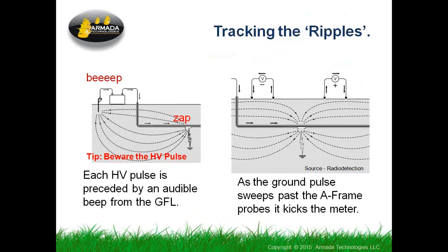I should mention that because that's a 2400 volt pulse, at least, coming out of the unit, you want to be careful with handling this. Once you've got it set up, you connect it like a locator, and a locator puts out a high voltage too, but not this high. You connect it like a locator and start doing your work out in the field, looking for the place where the ripples are occurring in the ground, and tracking down that unknown location of a fault.